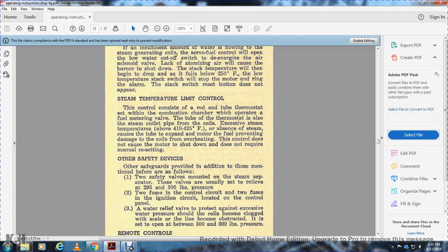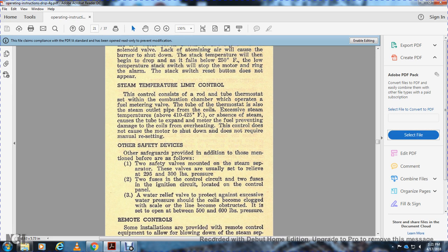Other safety devices. Other safeguards are provided in addition to those mentioned before. There are two safety valves mounted on the steam separator, usually set to relieve at 295 to 300 pounds of pressure. There are two fuses for the control circuit and two fuses for the ignition circuit located in the control panel. A water relief valve protects against excessive water pressure should the coils become clogged with scale or the line become obstructed, and is set to open at 500 to 600 pounds pressure.